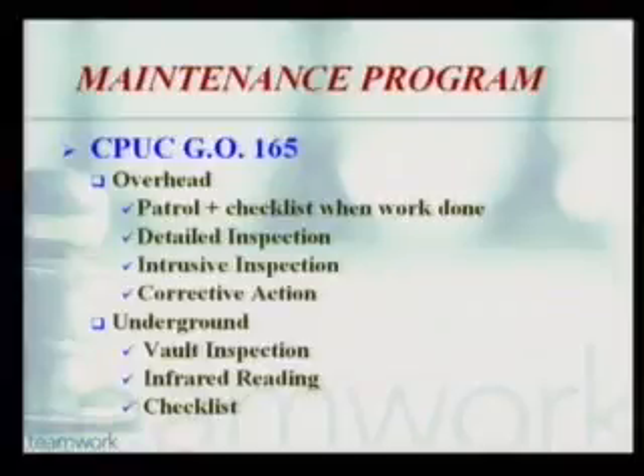On the power poles, we have cross arms, wires, capacitors, transformers—a lot of devices attached to these poles. What we do, although not mandated by GO 165, is every time we touch a pole we go through an inspection. We have a checklist, and we keep that on file for at least a year to show that we have inspected it.